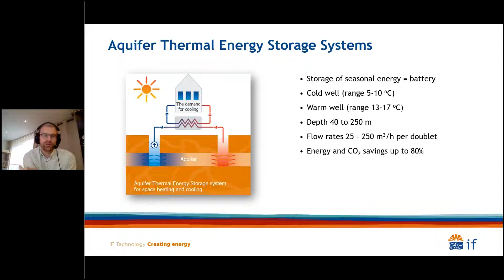Typical depths of the wells are between 40 and 250 meters. When we speak about this technology, we often work on projects with flow rates roughly between 25 and 250 cubic meters per hour. So these are large, bigger systems which can fulfill the complete energy demand of buildings.